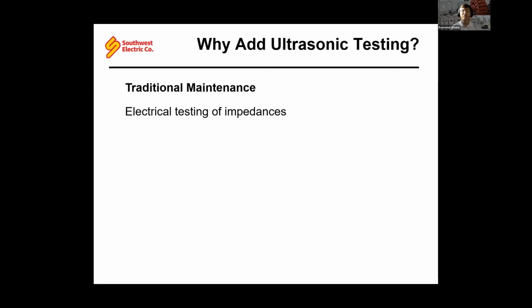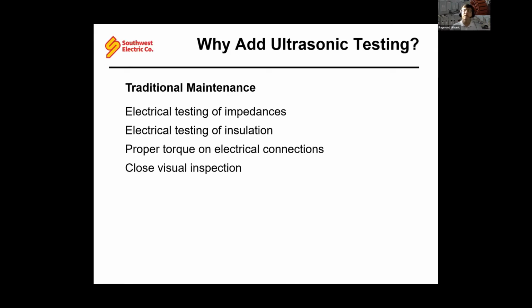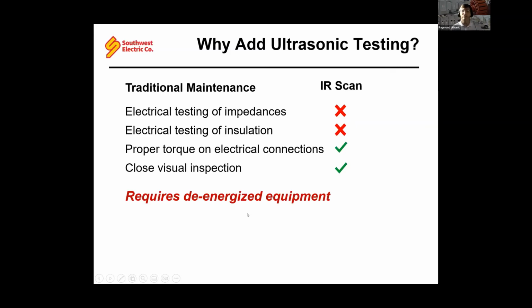So traditional maintenance and testing, all of these things, are usually done by IR scans, the torque and the visual inspection. But in terms of impedances and insulation, those are not available for IR scans. And the only way to test if you've got any kind of difference of impedances, if your insulation is starting to break down, is through electrical testing. And the only way to do the electrical testing is through de-energized equipment. There really is no other safe way.